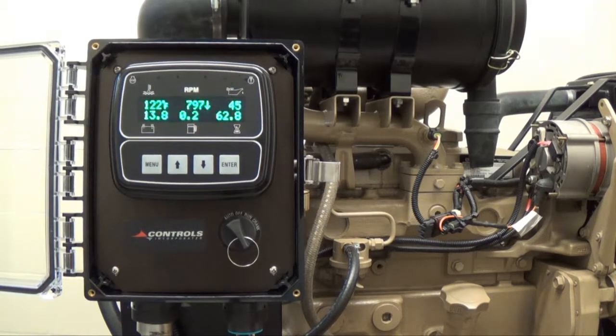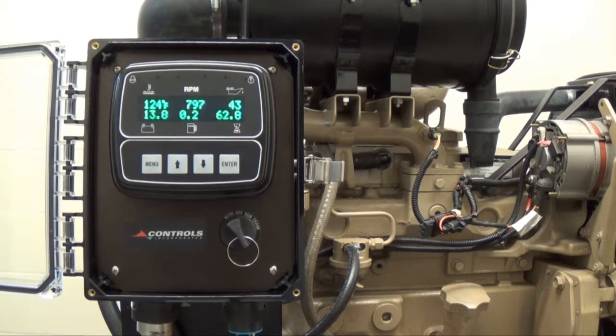As the pressure builds, the engine will run until it hits the high pressure contact and the high pressure switch will close to ground. The engine will ramp down, cool down, then shut down, and the controller will go back into sleep mode after 2 minutes of inactivity.